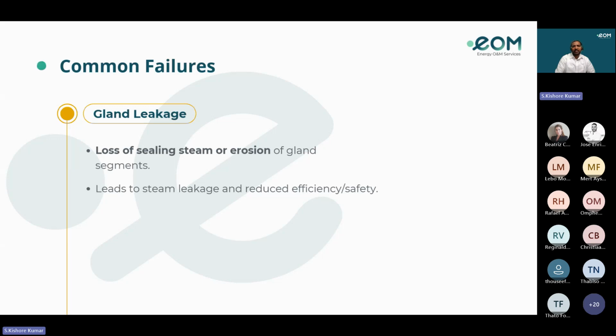And as I said earlier, regarding steam gland clearances, if the alignment is not done properly, the rotor will rub against the steam glands or the oil glands, and that will create leakage in the steam glands or in the oil glands. When the clearances of the oil glands or steam glands are on the higher side, sometimes the steam will slowly travel along the axis of the turbine, enter the oil seals, mix with the lube oil, and contaminate the oil. And sometimes if you do not maintain the proper lube oil pressure, that will pressurize the oil and it will gush out of the oil seal if the oil seal clearances are higher. It will pass along the rotor and enter the gland sealing steam.